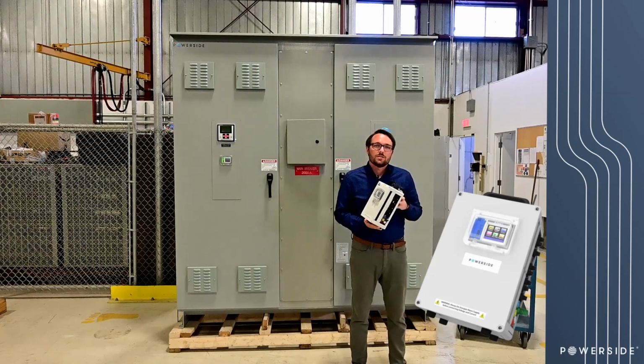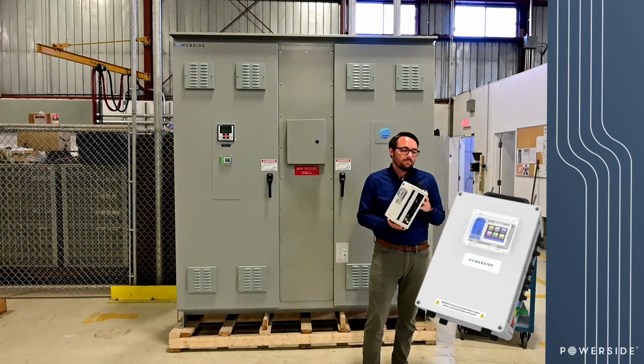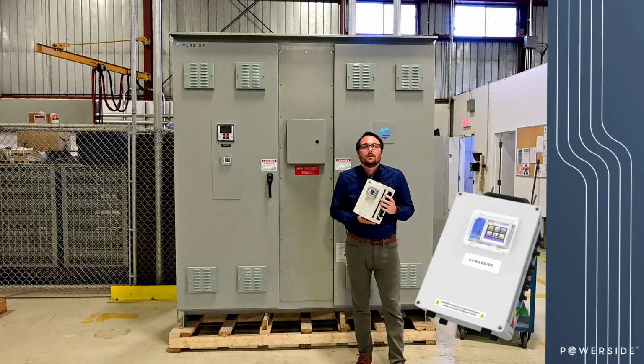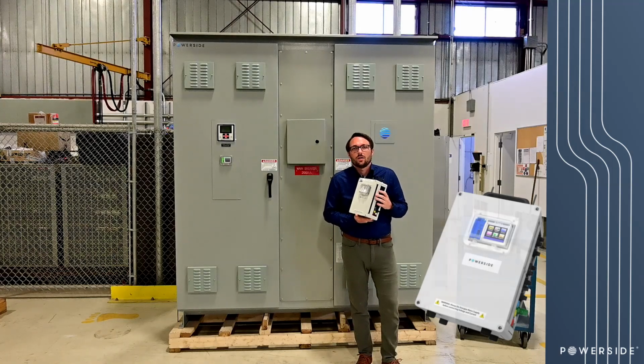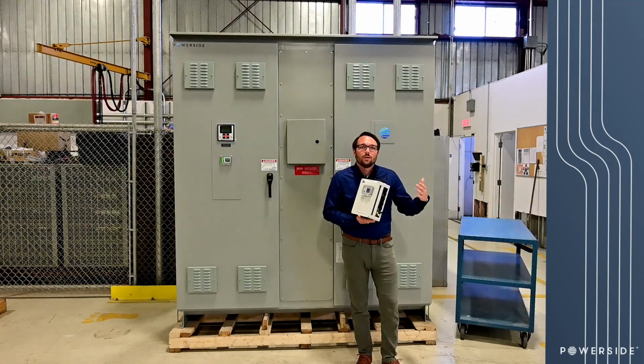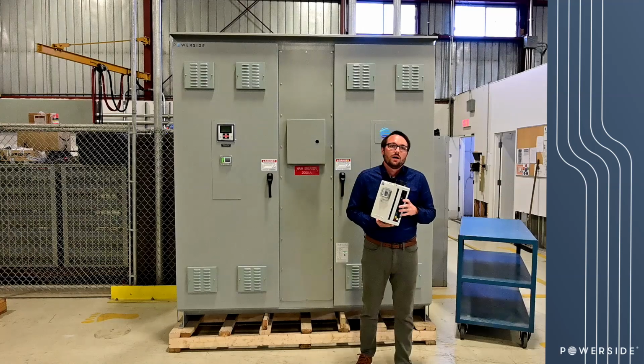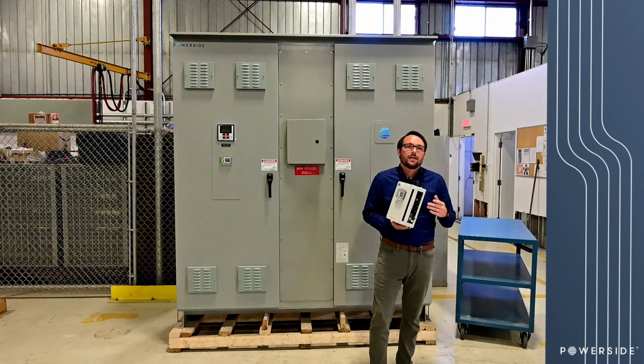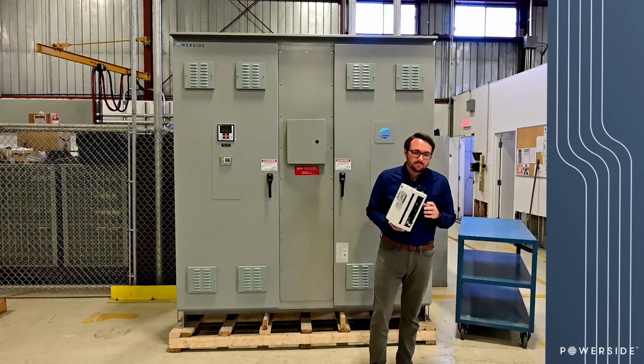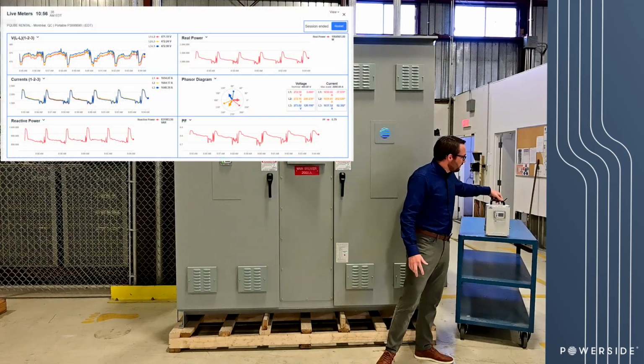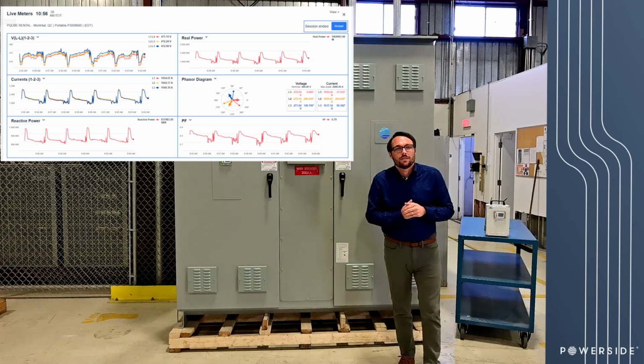They installed it on each of the main services going into the facility, and we were able to capture a significant amount of data to better understand what it was that they were experiencing from a load profile, as well as any other voltage conditions, power factor, harmonics, etc. On the screen here, you'll see an image of what we had captured with that data.